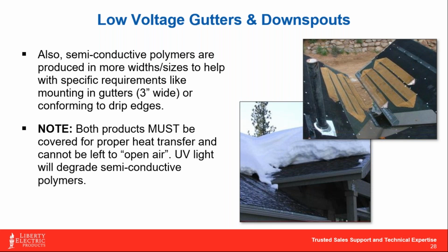One thing I didn't mention about the self-regulating low-voltage polymer product is why it was designed to be low voltage versus typical 120 volts and above on the AC side: keeping it low voltage means it never incurs the degradation process. We've talked about how self-regulating low-temp cables running between 120 and 277 volts will degrade over time. This particular product runs between 30 and 80 volts DC. The magic number is 100 - once you cross that threshold, degradation begins due to heat. Stay below it, and the product should last indefinitely.